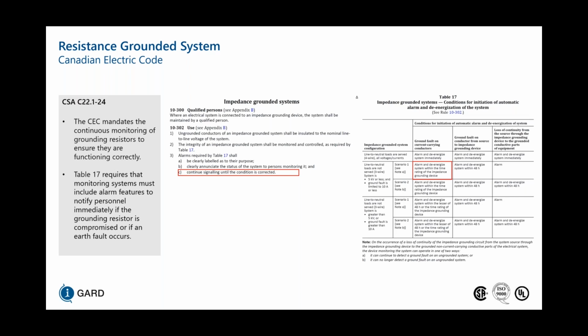So for impedance grounded systems, you could find the clauses in section 10 of grounding and bonding, particularly in section 10-302, where it says that you can continue signaling the condition of a ground fault until the condition is corrected. And in table 17, which is a very useful table for consultants, you can see the conditions in which you need to initiate an alarm or de-energize your system based on the type of condition that you're currently experiencing. So in the first column here, it indicates for ground faults in the system. The second column is in relation to when you have a short-circuited NGR and your system becomes solidly grounded. And then the last column here is in relation to when your system loses continuity between the XO point to ground, meaning an open circuit condition.